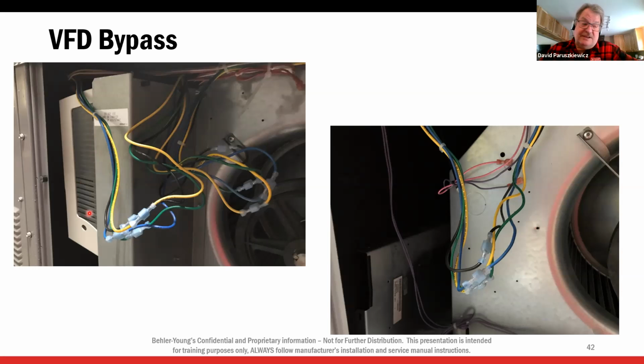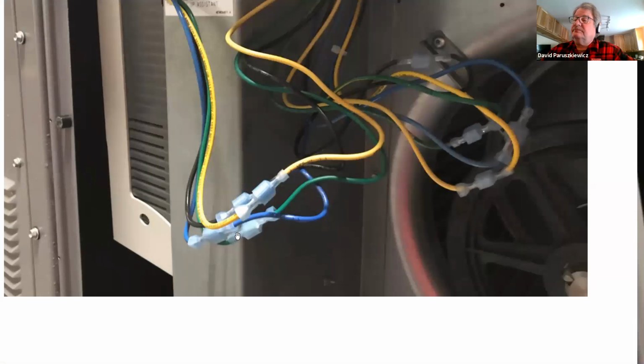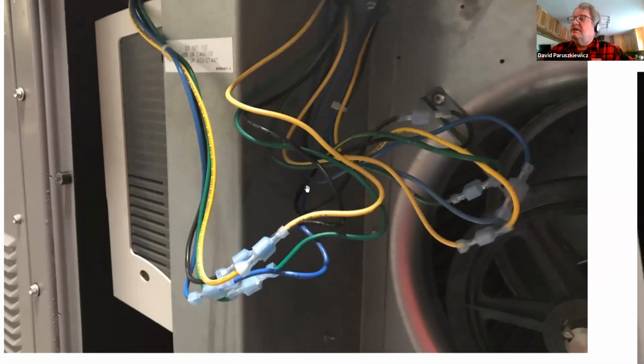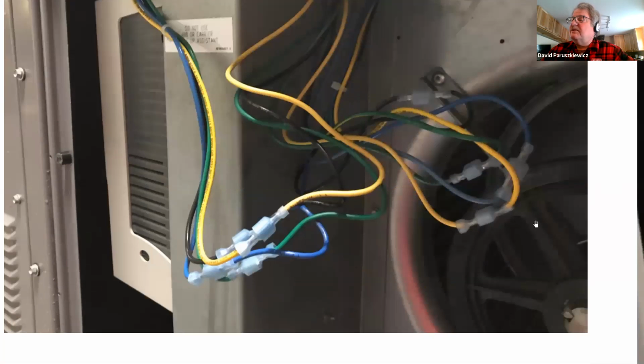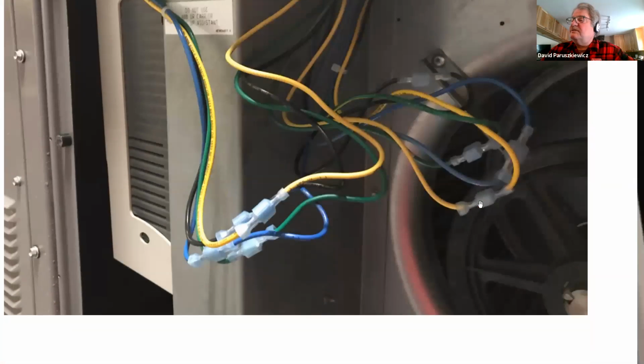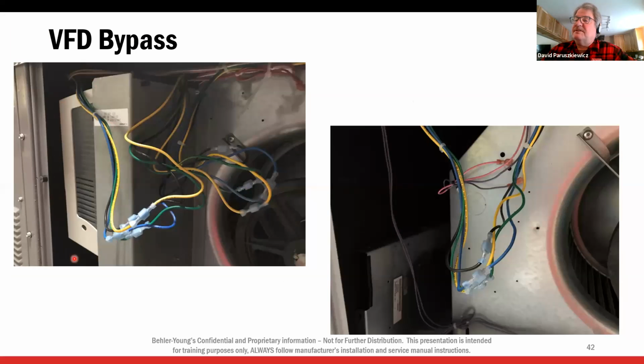Now, the drive, like I said, you're going to have to call and get it from us. Then you're going to have to program it. Well, in the meantime, this was kind of nice, if you look right here, you can see spade connectors. So there's my yellow, black, blue, L1, L2, L3. They're spade connectors. That goes up to the drive. And then coming out of the drive, they're spade connectors again, going to the blower motor. So I can simply unplug the drive and plug the motor in directly. Now if I look over here, you can see the left side is coming from the disconnect. Right side is going directly to the motor.